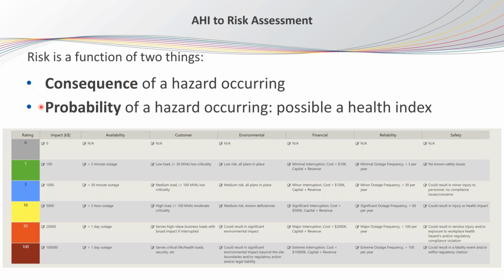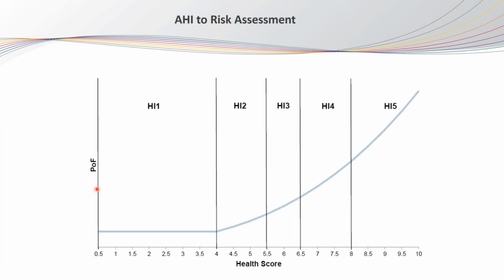The easy way to evaluate the probability of failure is through the health index. If you have a transformer with a bad condition, it means the health index is high, and so the probability of failure is also going to be high, and vice versa. A good health index means good condition and low probability of failure. This is just an example that shows how we can correlate the health index score with the probability of failure. As the health index score is low, the probability of failure is low. As the health index increases, the probability of failure is going to increase exponentially.